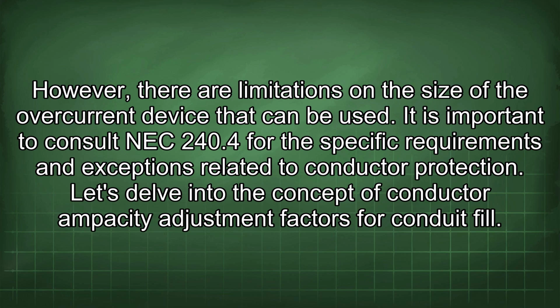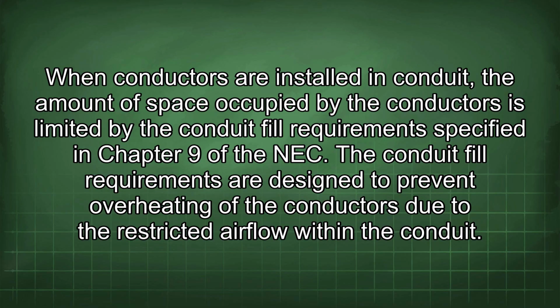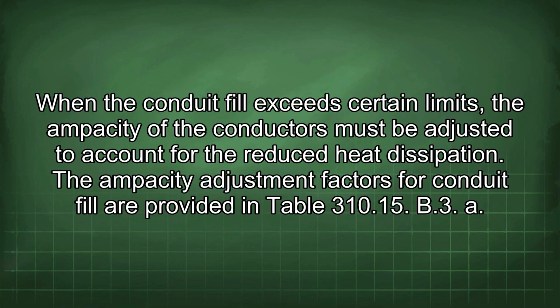Let's delve into the concept of conductor ampacity adjustment factors for conduit fill. When conductors are installed in conduit, the amount of space occupied by the conductors is limited by the conduit fill requirements specified in Chapter 9 of the NEC. The conduit fill requirements are designed to prevent overheating of the conductors due to the restricted airflow within the conduit.